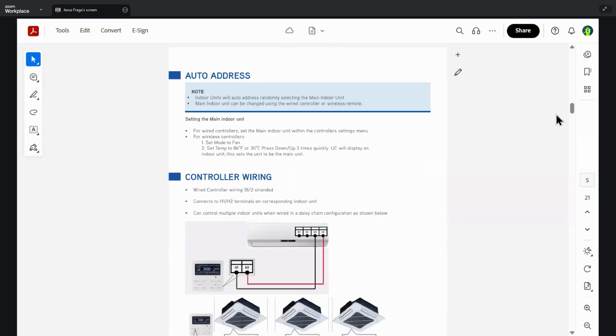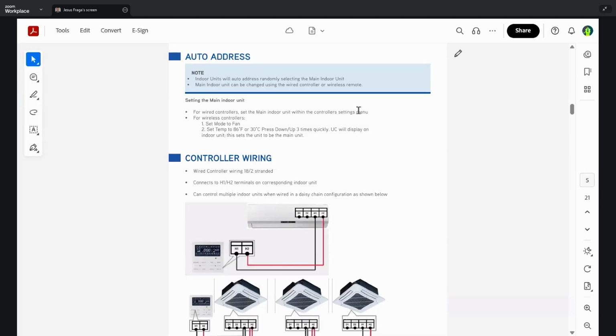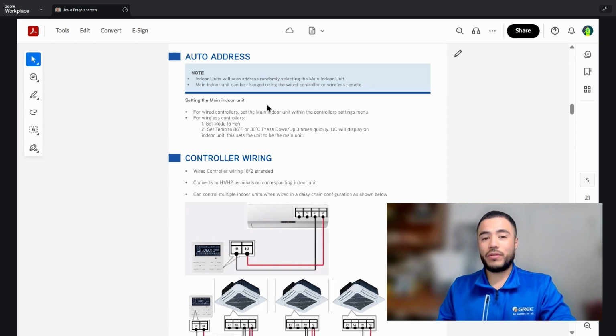So going on. So for auto addressing, it's a lot similar to the 410A models. The indoor units will auto address, randomly selecting the main indoor unit. Main indoor units can be changed, use the wired controller or wireless remote. So what this means is you can actually go into the wired controller, before you actually go through the commissioning, and designate what address you want for what area. That way, if you're mapping out a site, you can do that with ease instead of it doing it randomly. But an added feature and something that I always mention is that it'll do it automatically. So there's no need to manually do this. You can do it for mapping out purposes, but it's not necessary.